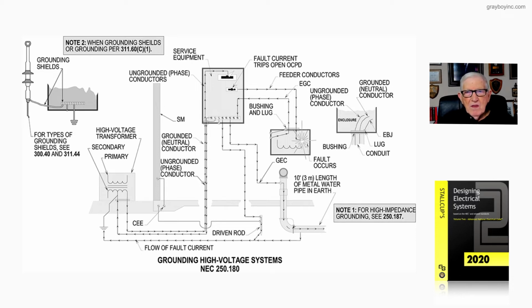Now, what we're trying to do here, when you run the equipment ground over here, then that's table 250.122. And the equipment ground would be sized off of this breaker that you see on the panel board. And if you developed a short circuit, it would return over your equipment ground back to the grounded bar that you see in the service equipment, travel over the grounded conductor back to your transformer, return on the phase it went to ground, and localize your fault.